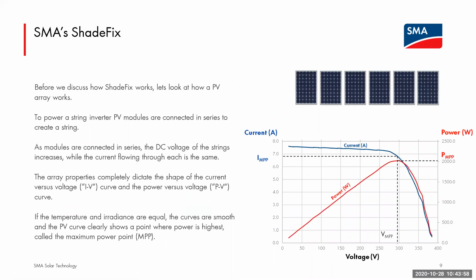So for the folks on the call that maybe have been in the solar industry for quite a while, or for the folks that are a little bit newer to the industry, I want to talk about what the inverter is seeing. So you take modules off the pallet, you string them together. Sometimes you have a string of 12, sometimes you have a string of 18 modules. When you connect those modules in series, at the end you have voltage, and when the inverter turns on, you have current. But what is the inverter doing, and what is it seeing? And when there's shade, what's this ShadeFix algorithm doing? So over the next few slides, I'm going to explain that.